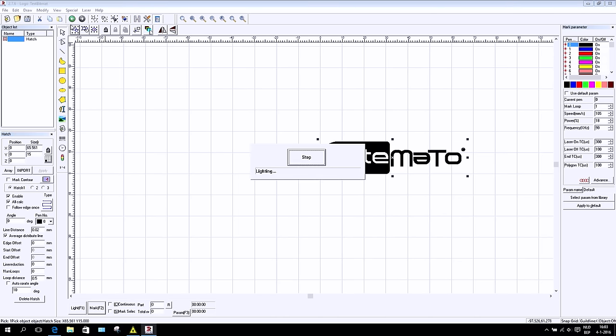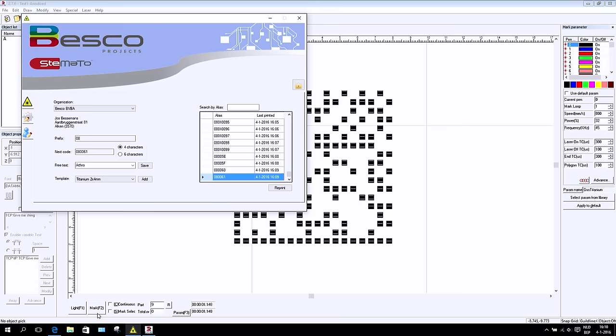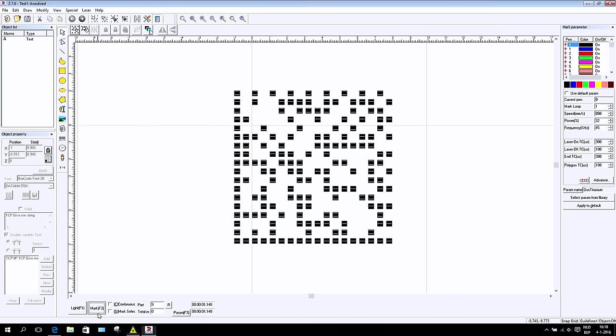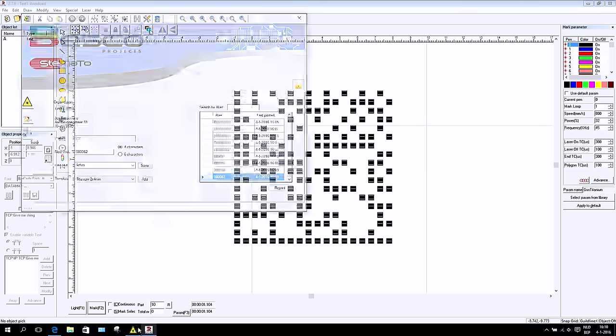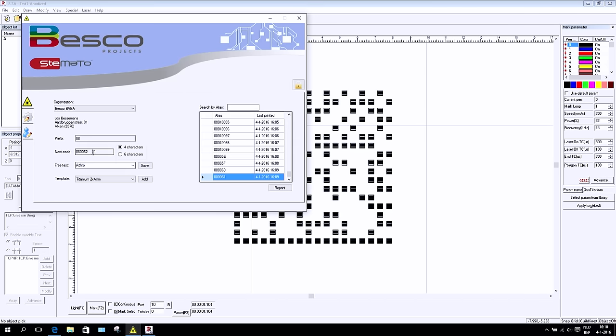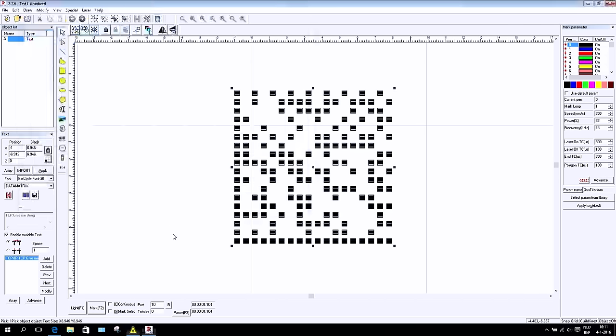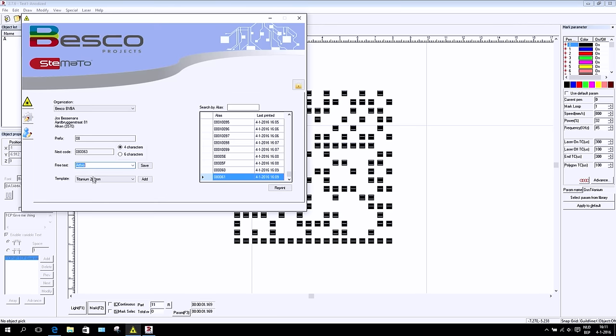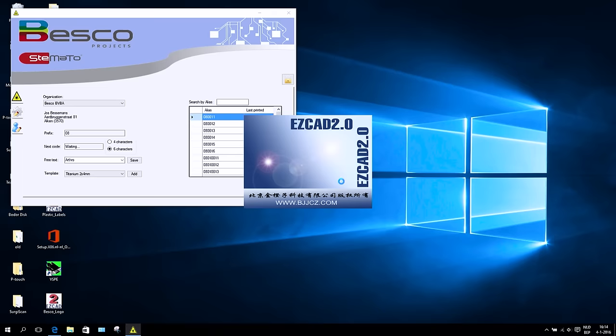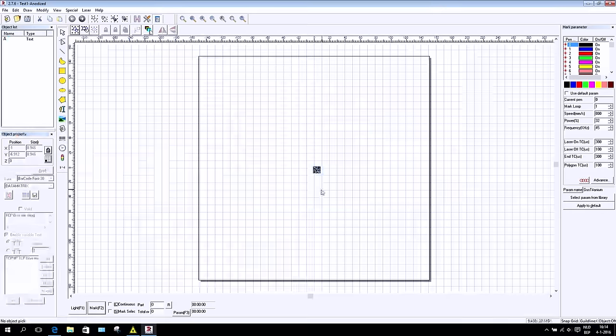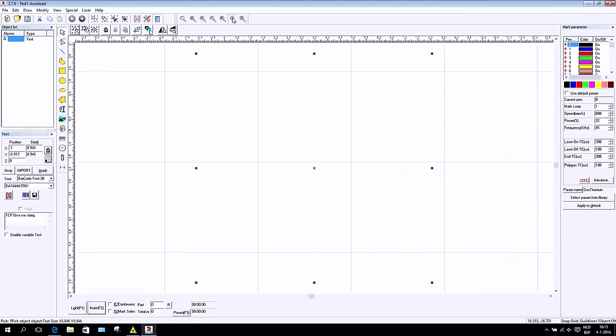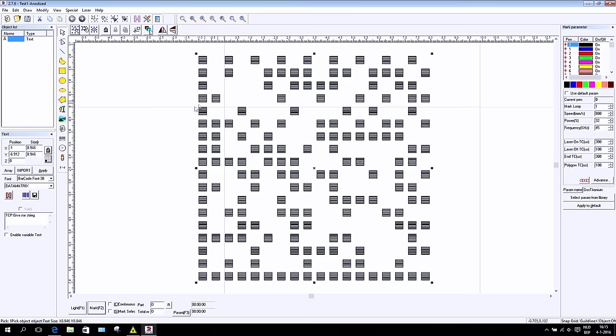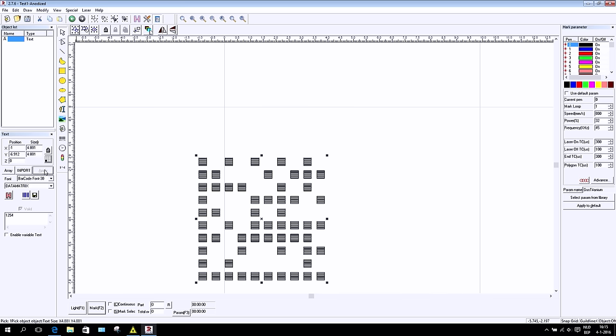The Besco Laser Management Software is to create automatically and to manage the unique codes and other additional text you will use to mark. Your hospital identification, together with a 4 or 6 digit hexadecimal code, allows to laser all your instruments with data matrix in a range from 1 x 3 mm to 4 x 4 mm.